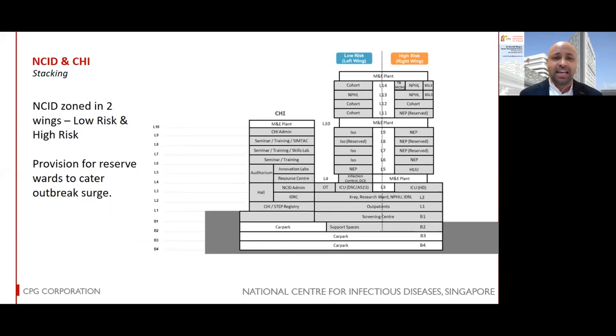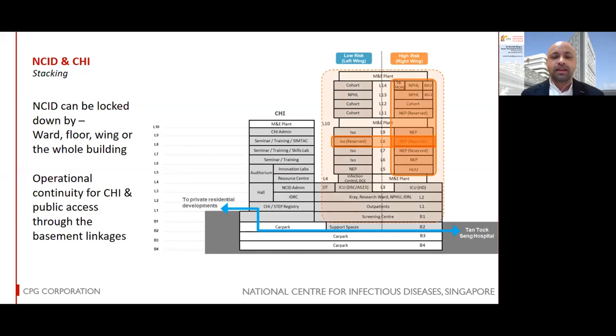NCID is designed in 2 wings, low and high risk. The right wing is designated as the high risk wing, which largely houses the negative pressure wards, a high level isolation unit, and a BSL-3 lab. Depending on severity of the outbreak, NCID can be isolated and locked down by 1 ward, 1 floor, 1 wing, or the whole building.